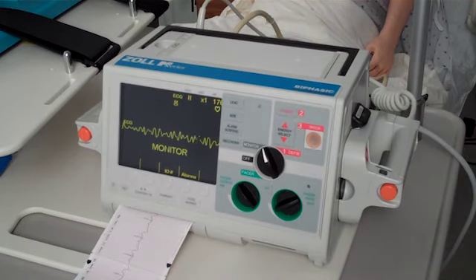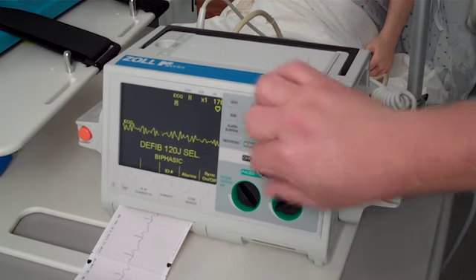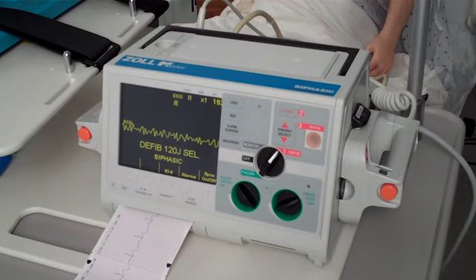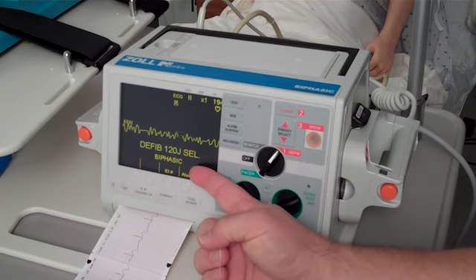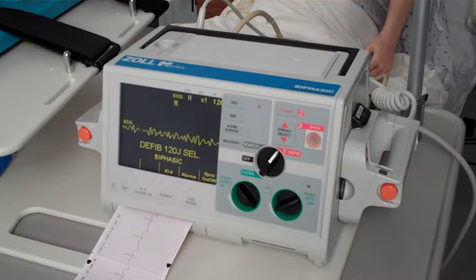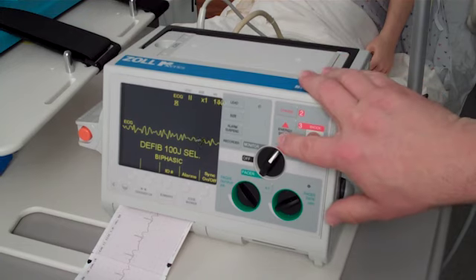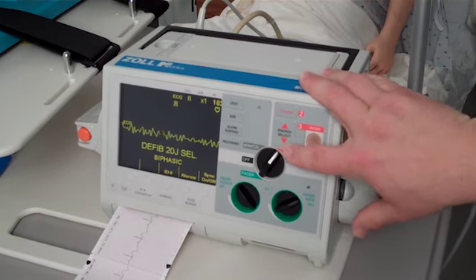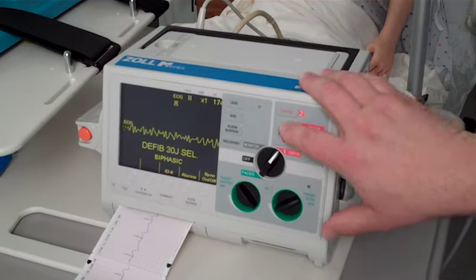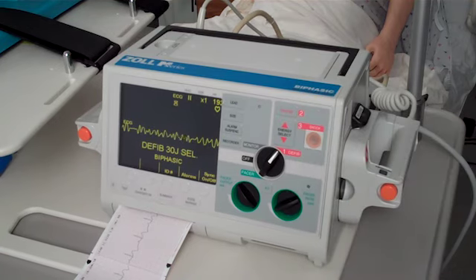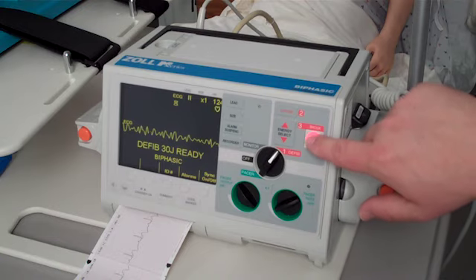Should your patient require defibrillation, turn the control dial to the defibrillation section. Notice that the energy setting comes up with a default of 120 joules on this biphasic defibrillator. In order to change the energy selection, use the down arrow or up arrow keys. Once the defibrillator is set at the appropriate energy level, press the charge button. Now that the defibrillator is charged and ready to go, clear the patient, and once the patient is clear, press the shock button.